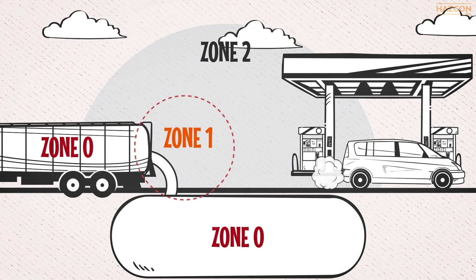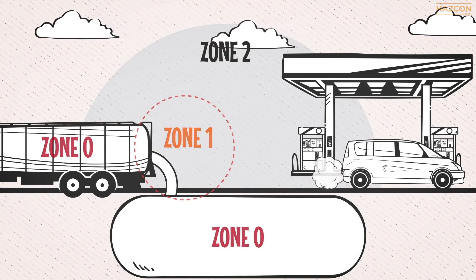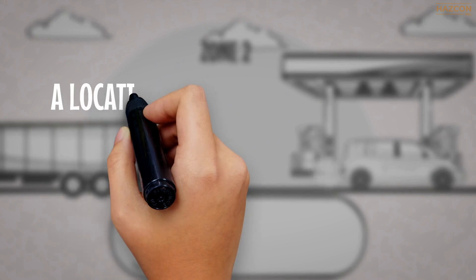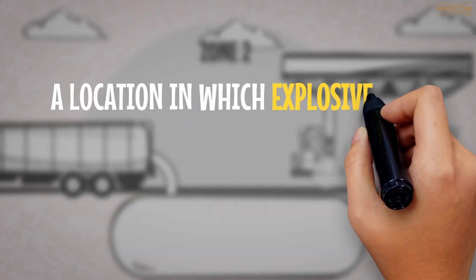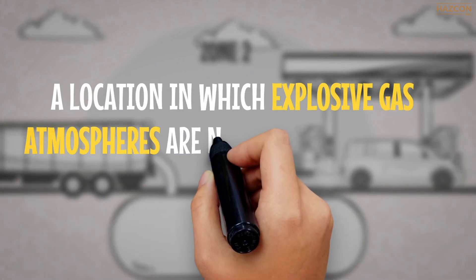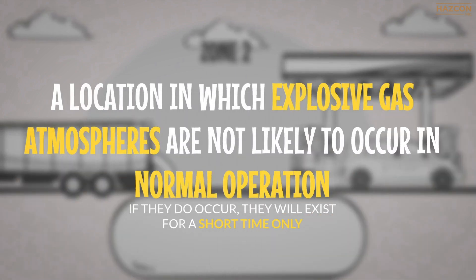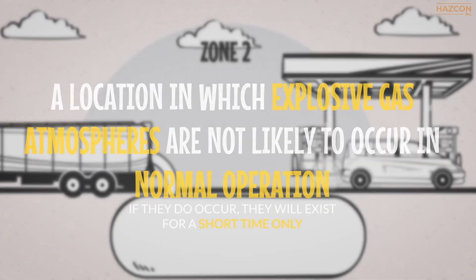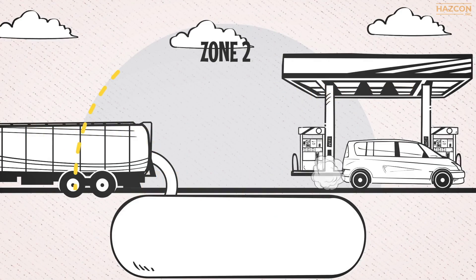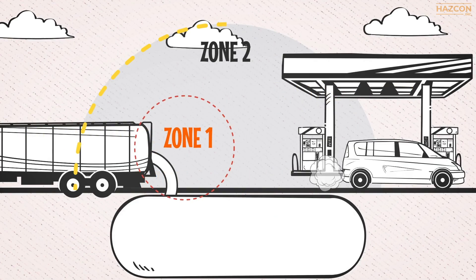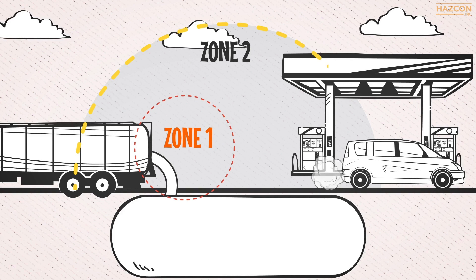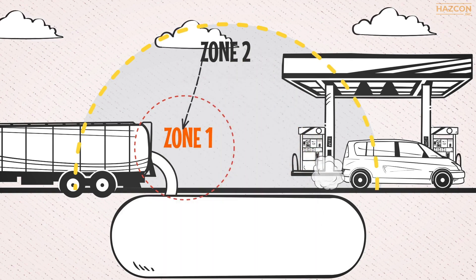In this animation, our focus is on the Zone 2 classified areas. Zone 2 is a location in which explosive gas atmospheres are not likely to occur in normal operation and, if they do occur, they will exist for a short time only. Zone 2 includes the area adjacent to a Zone 1 location, from which explosive gas atmospheres could be communicated.